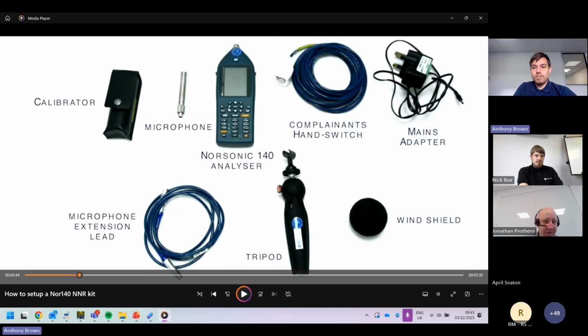You'll need your hand switch — hopefully you've got that, and it plugs into the side of your sound level meter. On the left-hand side there's a socket to plug the hand switch in, with a couple of small screws to secure it, though you don't need to screw it in. Normally the cable channel within the case holds the cable in place.